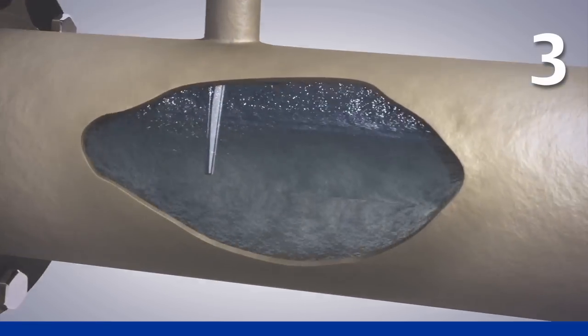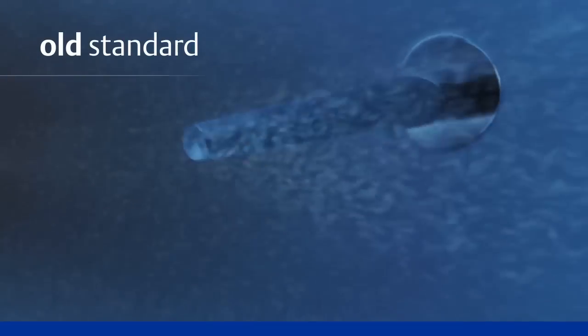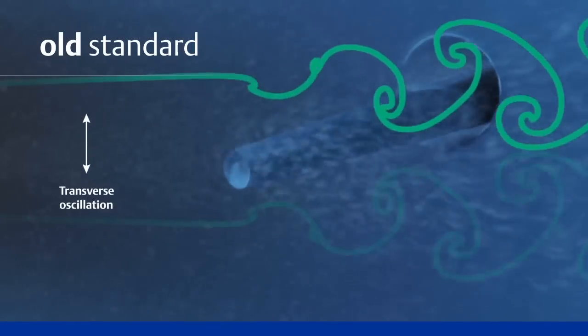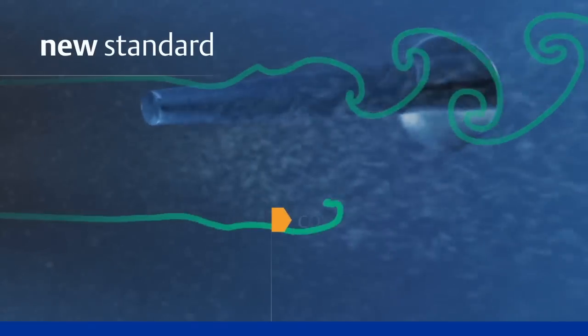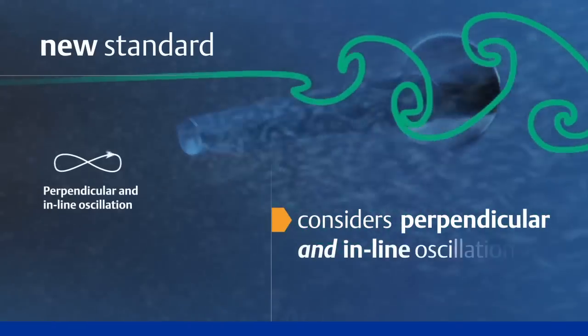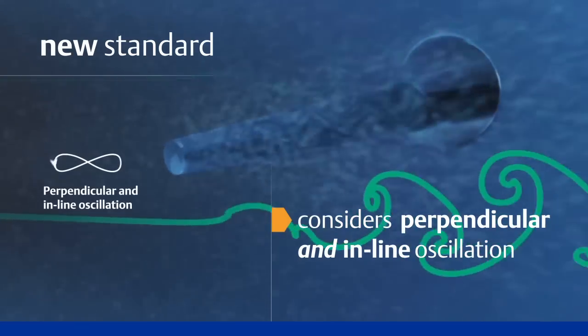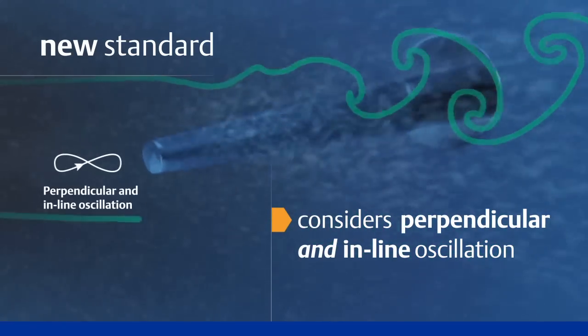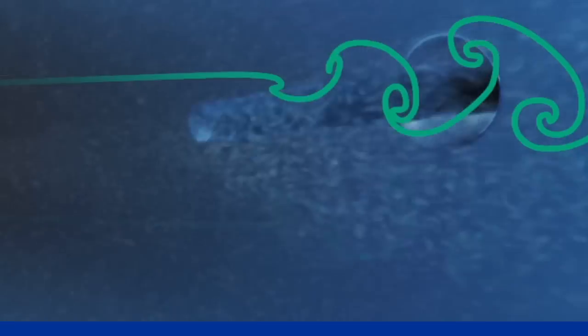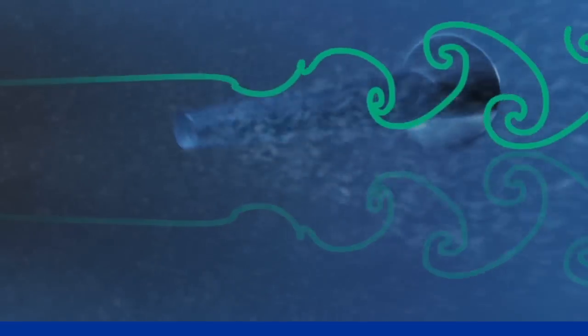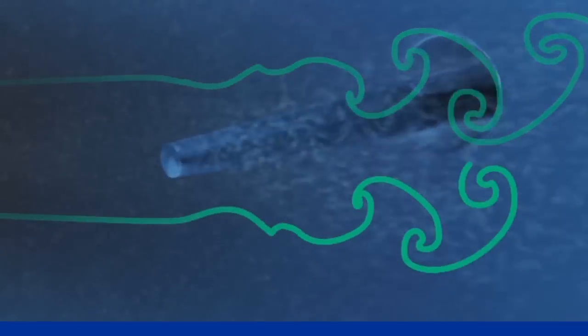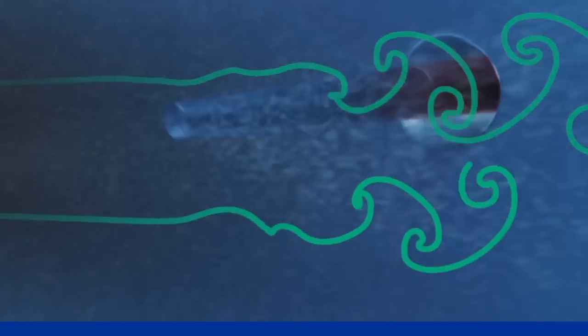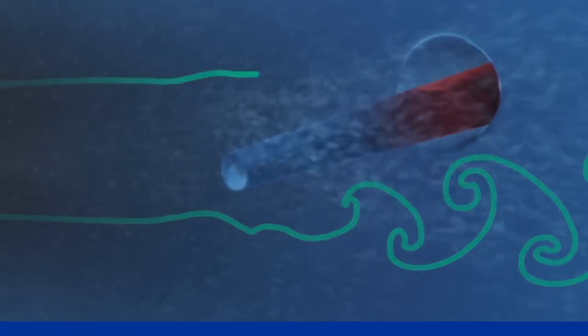Third, the 1974 standard only considered oscillation that is transverse, or perpendicular, to the flow. The new standard considers both perpendicular and inline oscillation. This is important because as a process ramps up, the thermowell goes through the inline vibration resonance first, then the transverse. If the thermowell cannot withstand the inline resonance, it becomes the new limiting factor.